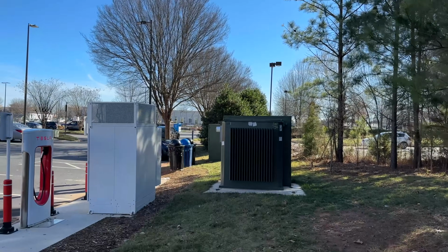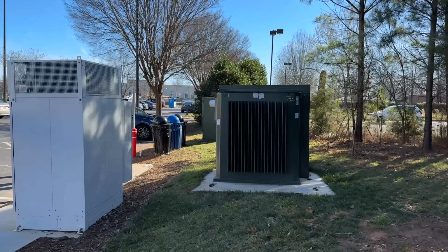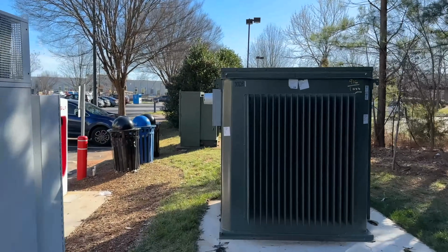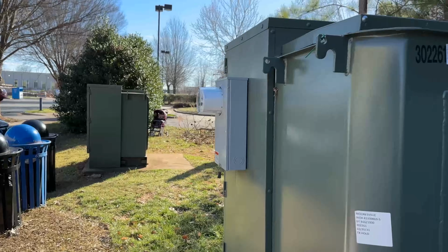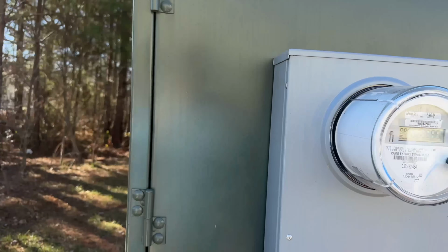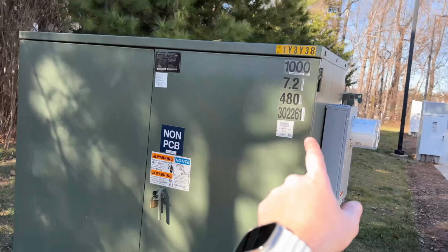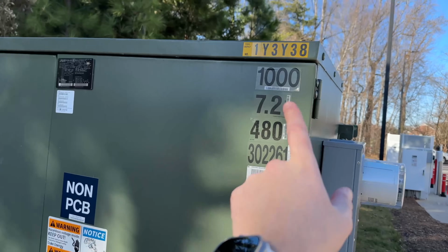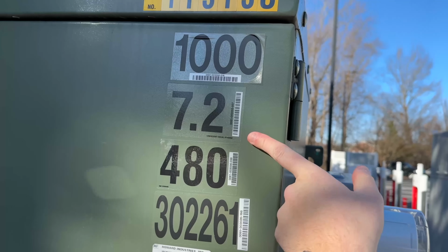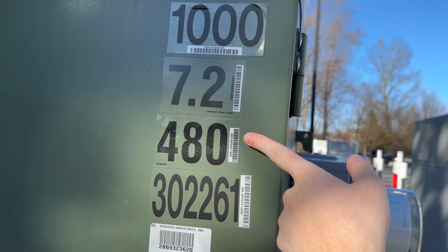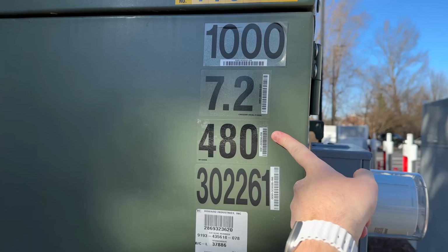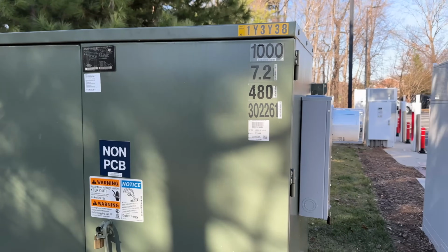We have a 1000 kVA utility transformer over here—let me show you that. This is from Duke Energy because we're in Mooresville, North Carolina. So 1000 kVA, you can see right there. Incoming primary voltage is 7.2 kV and we have a 480, 277 secondary voltage. Pretty typical for DC fast charging sites.